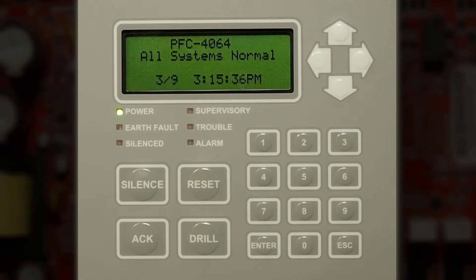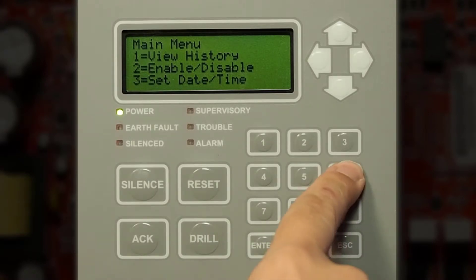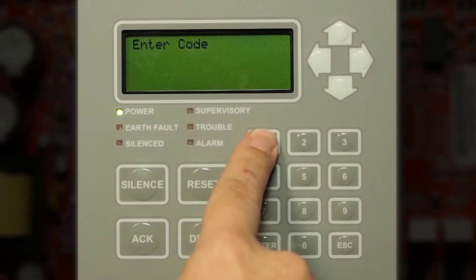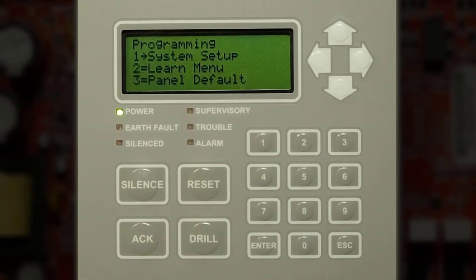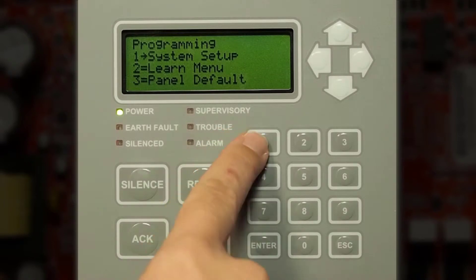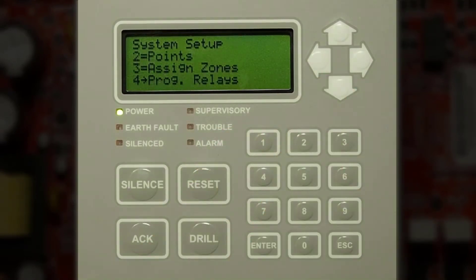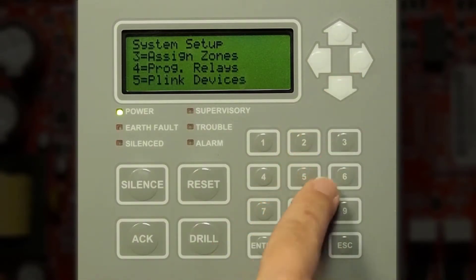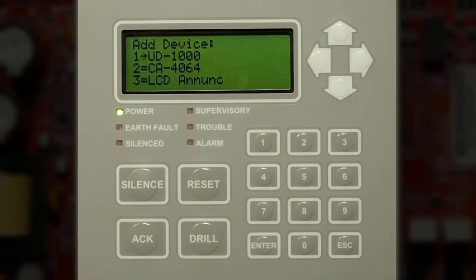First we will add and program a UD1000 module. To do this you'll need to press enter on the keypad, navigate to number six programming, enter the default code of 1111, then go to number one system setup, press the down arrows to get to number five P-Link devices, then you'll press number two add new device, press number one for UD1000 which is the dialer.